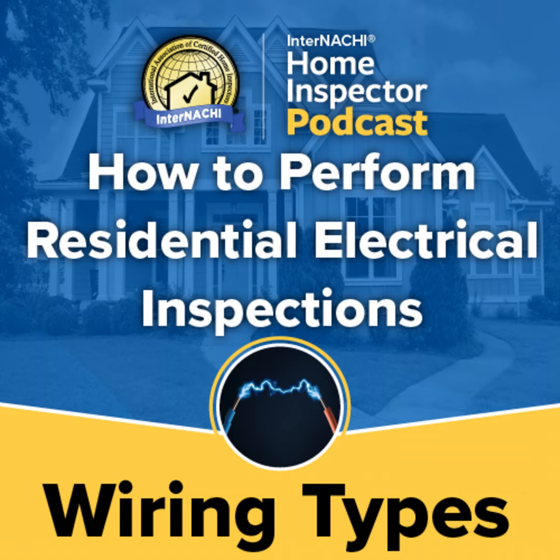Aluminum, a good conductor of electricity but has higher impedance to the flow of electrons, which means that larger conductors need to be used for any given amperage. Aluminum was used for residential branch circuit wiring from the mid-1960s to the late 1970s, but was found to be unreliable. We'll explore this later. Copper-clad aluminum. Coating aluminum in copper was an attempt to overcome the issue of oxidation of the aluminum conductors that was leading to failures. It did not have the failures associated with pure aluminum and is considered safe. However, copper-clad should be sized the same as normal aluminum.